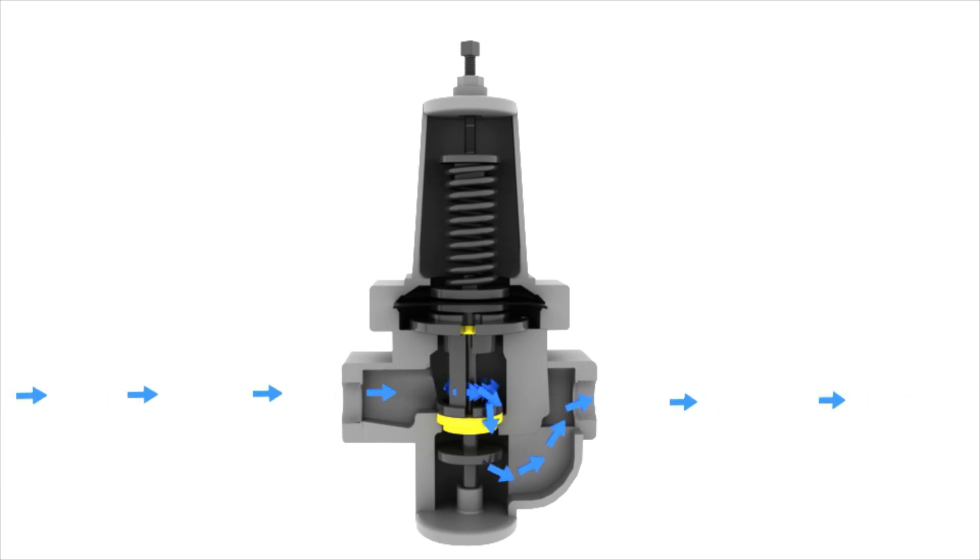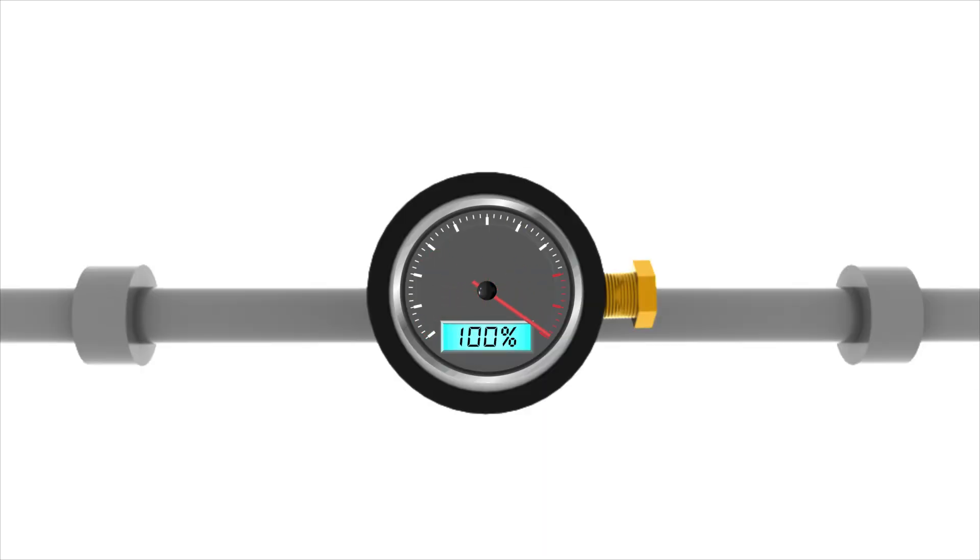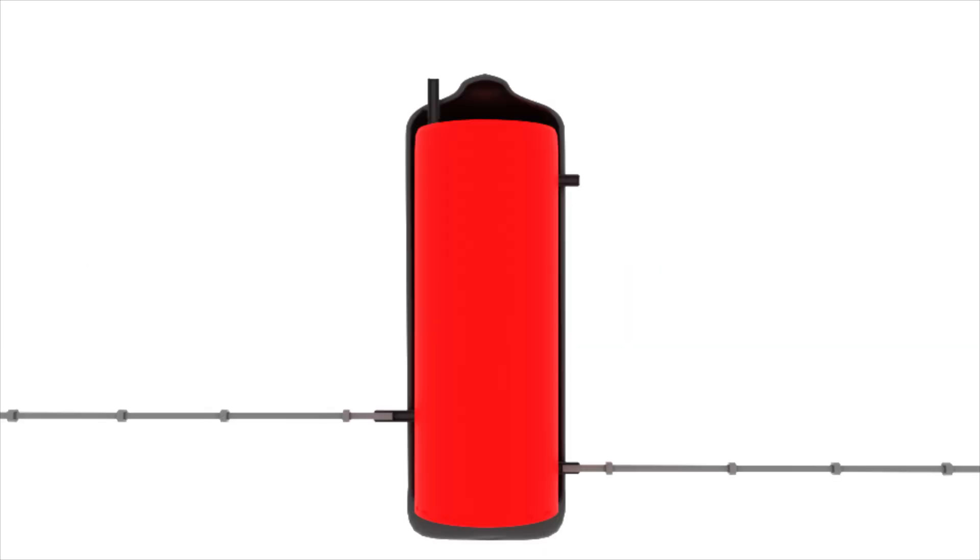Displacement purging is the replacement of the undesired gas by a purge gas without intermixing of the two. Dilution purging is the reduction in concentration of an undesired gas by the addition of a purge gas, like N2.